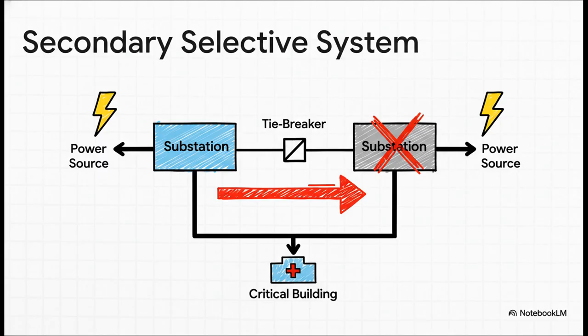But for places that absolutely cannot lose power — think data centers, hospitals, trading floors — you go for the gold standard: the secondary selective system. Here you have two full substations working together. If one of them fails completely, the system automatically shifts its entire load to the other one in just a matter of seconds. This is how you get as close to 100% uptime as possible.